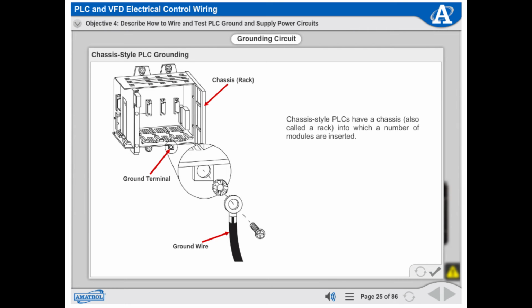Chassis-style PLCs have a chassis, also called a rack, into which a number of modules are inserted. This type of PLC is usually grounded at the chassis. The chassis itself is connected to a ground point that is wired to earth ground.